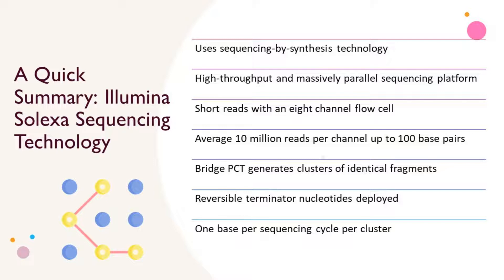Illumina Solexa sequencing technology is deployed in the Illumina Genome Analyzer, a high-throughput, short-read, massively parallel sequencing platform. It uses sequencing by synthesis on an eight-channel flow cell to produce more than 10 million reads per channel with read lengths up to 100 base pairs. Individual fragments of a genomic DNA library are amplified on the flow cell via bridge PCR to generate clusters of identical fragments. Reversible terminator nucleotides are used, allowing the reading of one base per sequencing cycle per cluster.